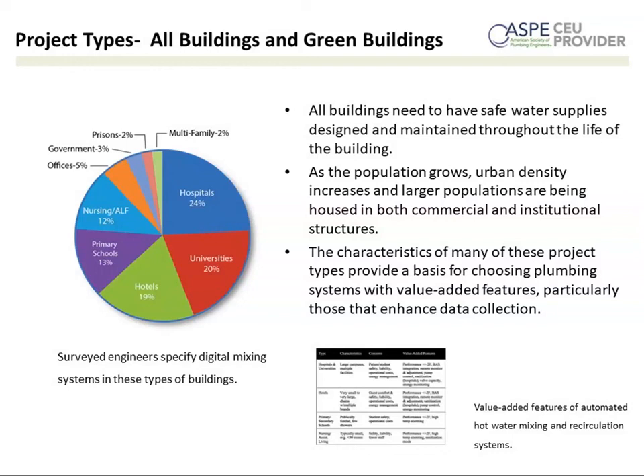Yeah, so I would say our experience has been healthcare and hotels, clearly, and universities. Those would be obviously the three big ones that we've experienced. But clearly, I think the message here is that digital mixing is appropriate for all facilities. And now with the advent of new smaller capacity valves, as opposed to putting digital mixing into hospitals, we're able to put digital mixing into assisted living and nursing homes where smaller capacities are more appropriate, where maybe you don't need all the bells and whistles of a larger system. You may not have a building management system to tie into. So some of those things are becoming more important.